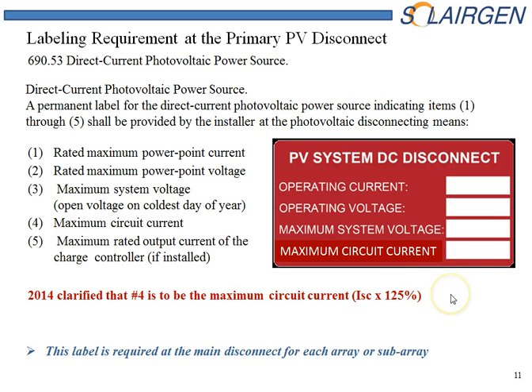Here we're showing another DC disconnect label, and this one has the operating current, operating voltage, max system voltage, and max system current on it. So this is standard test condition. The first two are standard test condition readings. The last two are the coldest day voltage, and the maximum current, which is ISC times 125%.